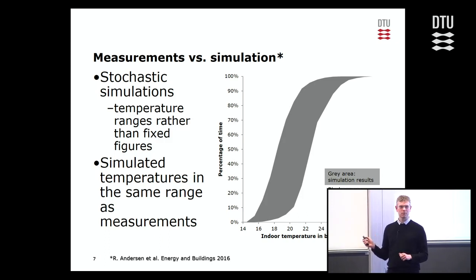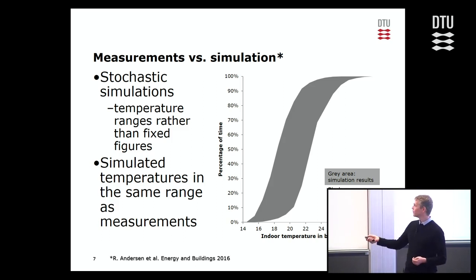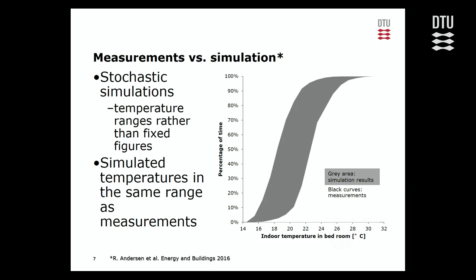Since these were probabilities of an event occurring, we used stochastic simulation - so instead of getting one temperature in each time step, we got a probability distribution of temperatures. That's why the result is not just one curve as in a normal simulation, but an area of simulation results. The measurements are shown here. One of the apartments was not captured by the simulations, but in four of them the majority of the temperature measurements actually coincided with the simulations.